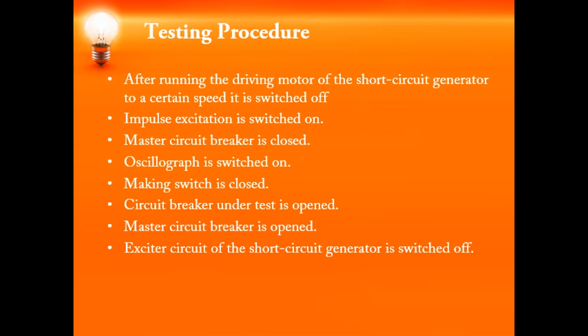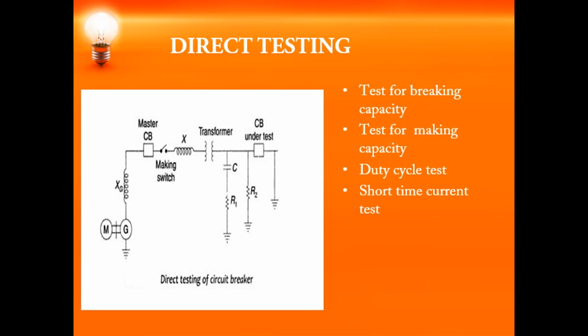Next, as I've told you, we will see what is meant by direct testing and indirect testing of circuit breakers. So, direct testing. Direct testing means the circuit breaker is tested under the condition which actually exists on the power system. You see here, you have the generator which is driven by the motor, the reactance, the master circuit breaker, the making switch, a transformer, and the circuit breaker under test. What is being done here? Your circuit breaker under test is subjected to the restriking voltage which will actually exist practically.